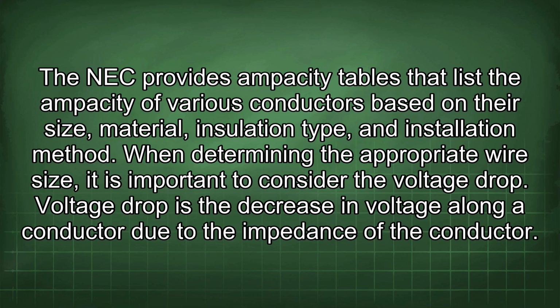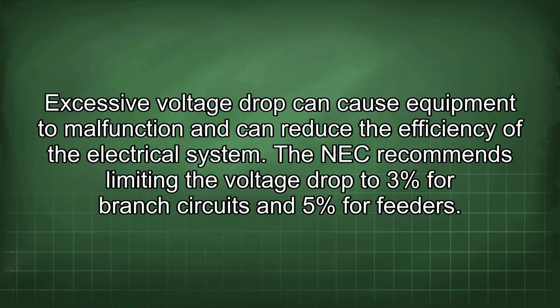When determining the appropriate wire size, it is important to consider the voltage drop. Voltage drop is the decrease in voltage along a conductor due to the impedance of the conductor. Excessive voltage drop can cause equipment to malfunction and can reduce the efficiency of the electrical system. The NEC recommends limiting the voltage drop to 3% for branch circuits and 5% for feeders.